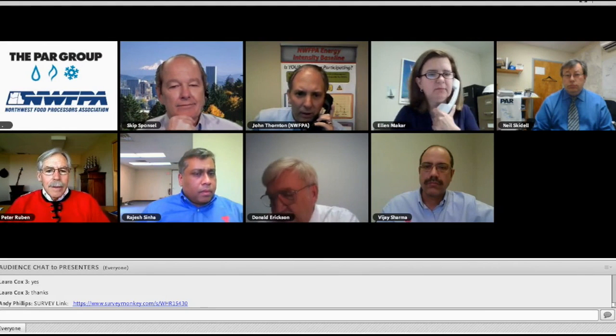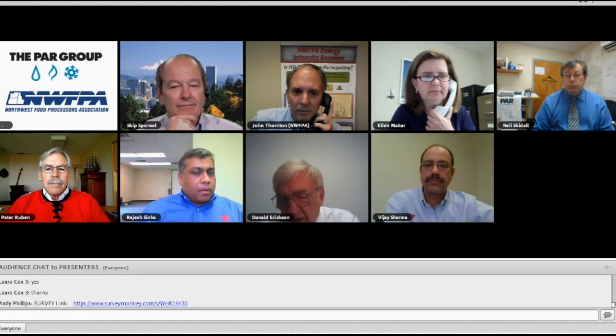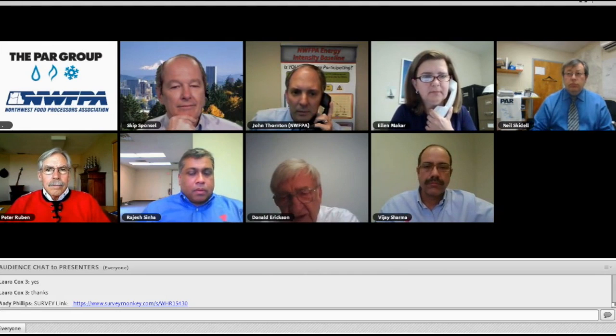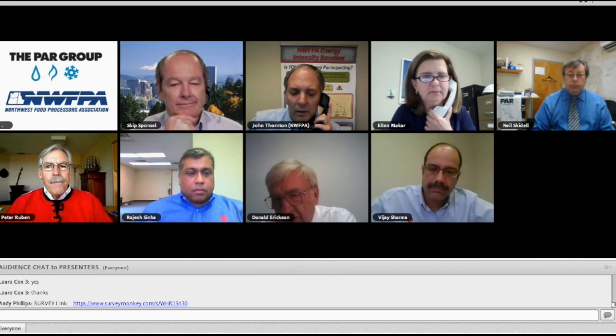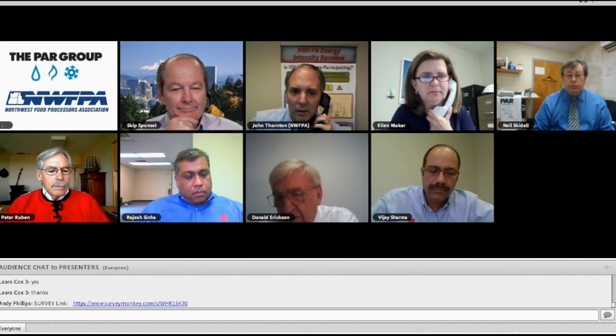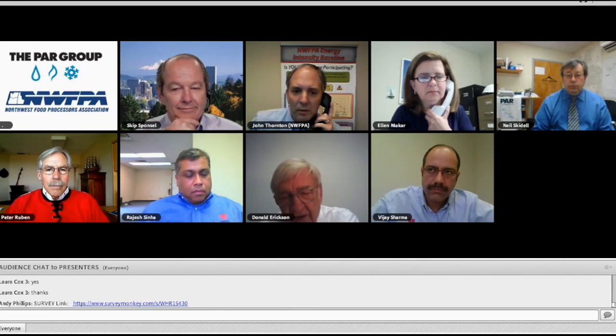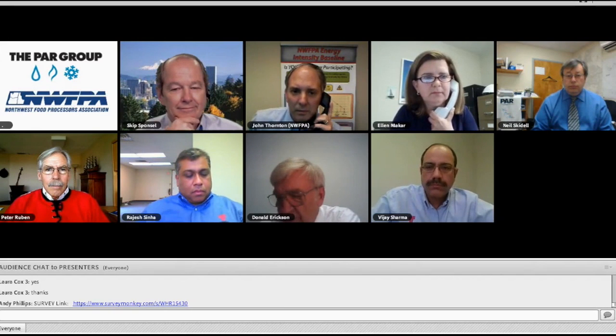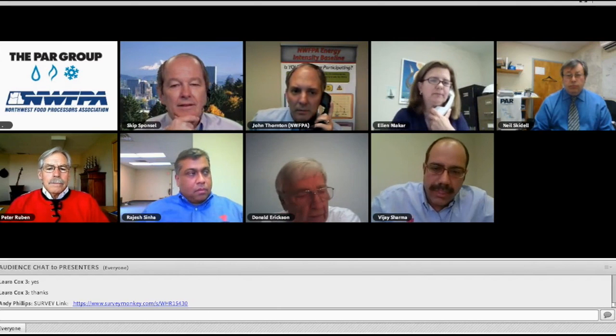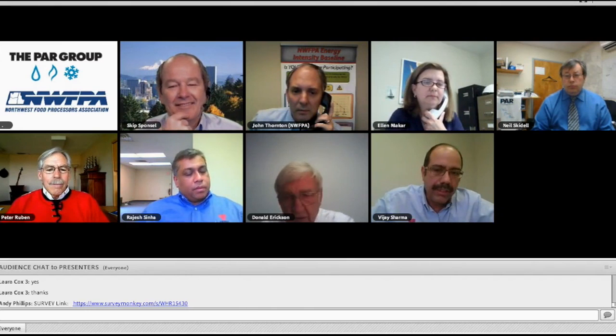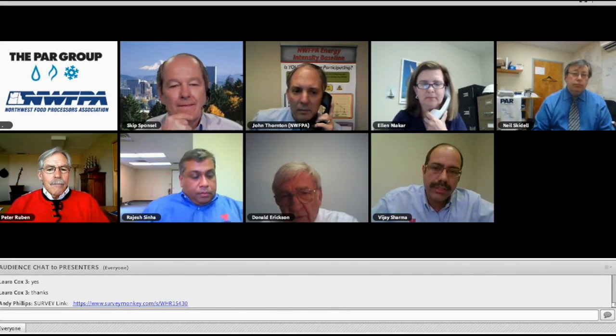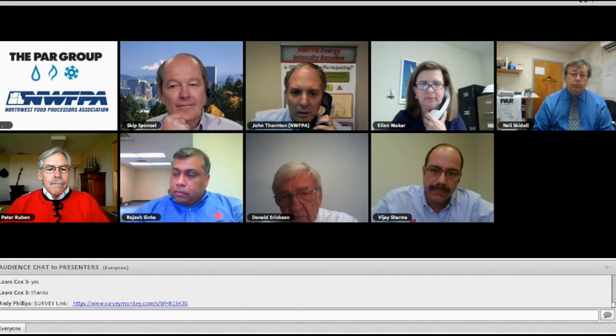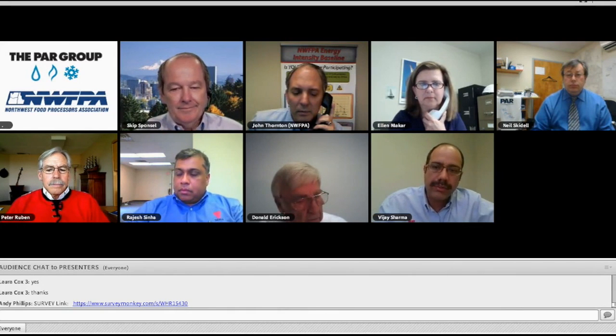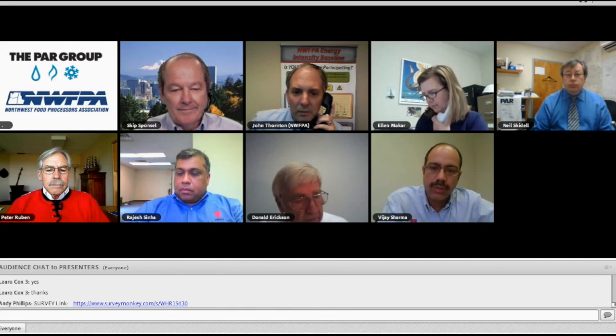Yes, no, thank you. Let me answer that from the Energy Concepts perspective. We've done a couple of different types of installations. Most usually, we will have a hot water storage tank as part of the system, so we can keep producing the chilling during variable hot water demand. Then when the hot water storage is completely full, we either just turn the unit off, or we have backup cooling tower water at that point, whatever is more important for the customer. Yeah, so in the chiller heater absorber, we have a ratio for the changeover of 30 to 70%. So you can have either 30% cooling demand and 70% heating, or 30% heating and 70% cooling. And if there is no heating demand, the same chiller can run back in 100% cooling.